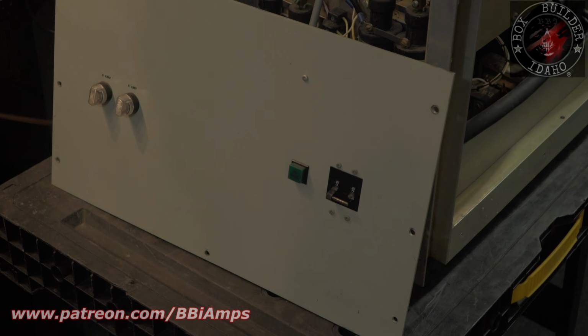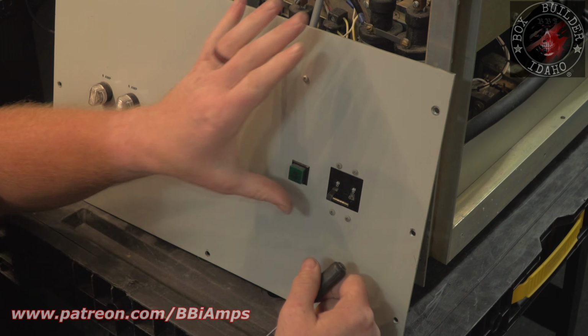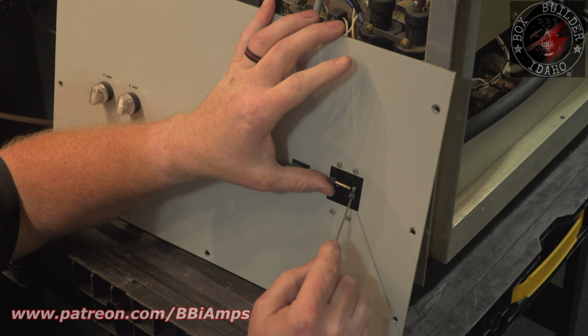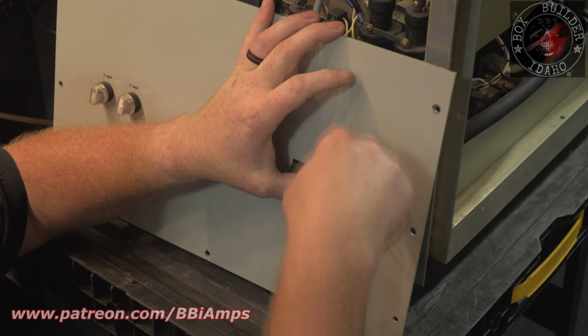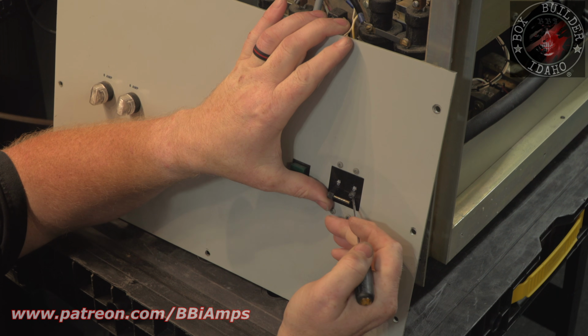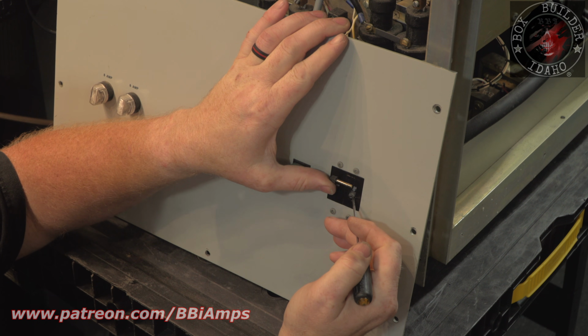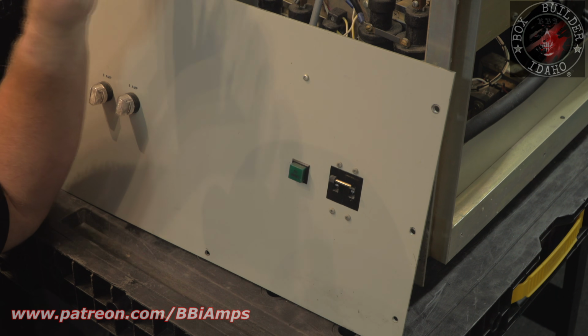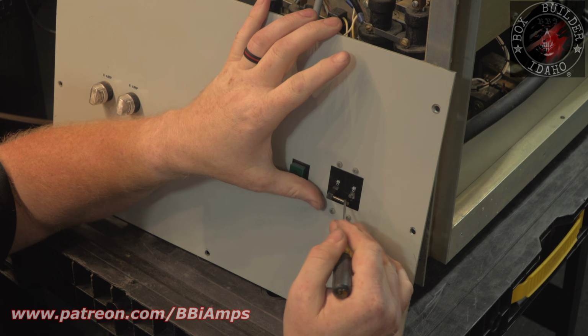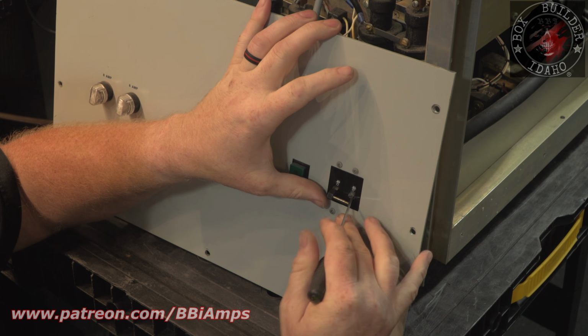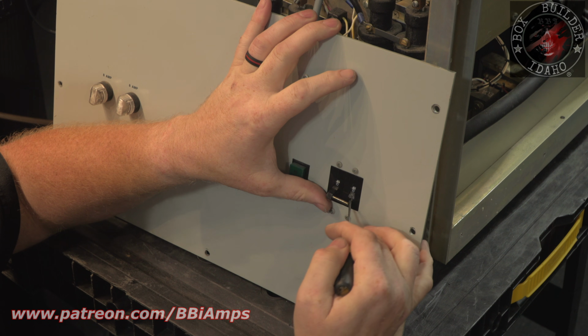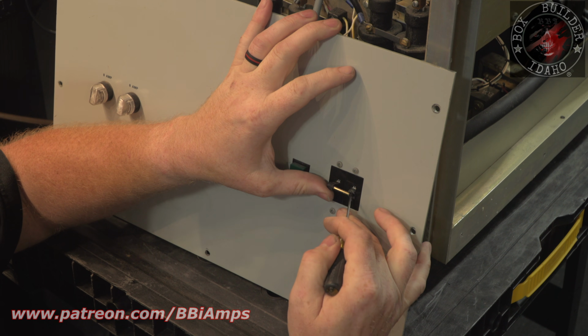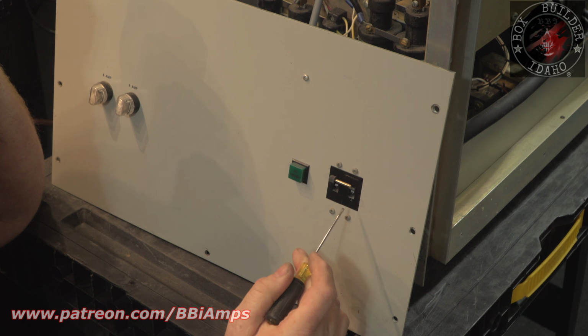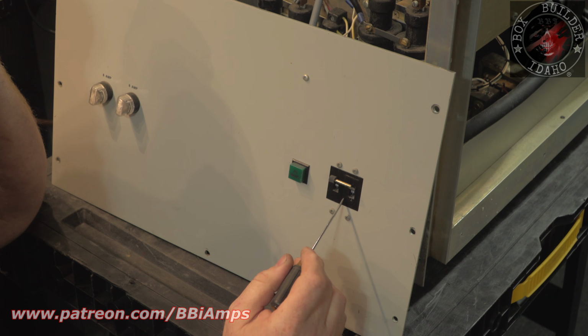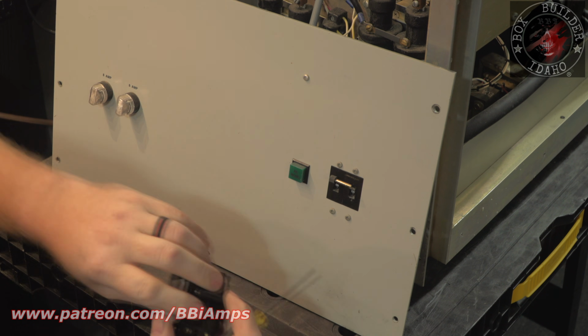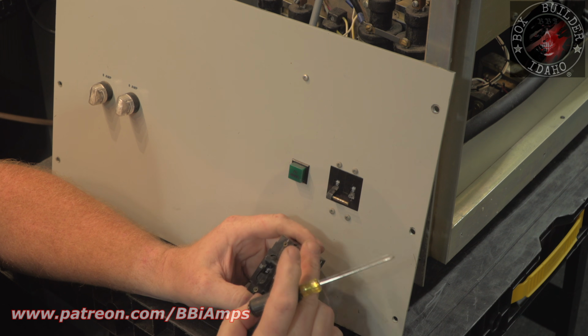Okay, so the first thing we've got to look at is our breaker. This arm has been broke off, and was broke off long before it showed up in my world. So if you try to cycle this by itself, it'll stay, but it doesn't take anything to trip it. And really, that won't stay engaged unless this arm comes up with it at the same time. So I've got to take this breaker out and install this breaker.